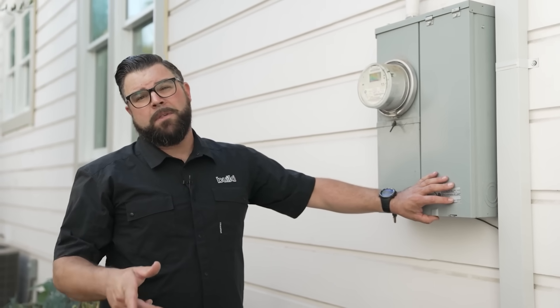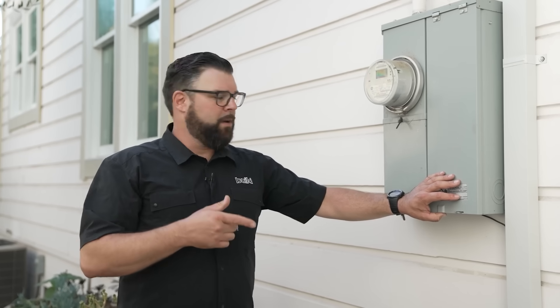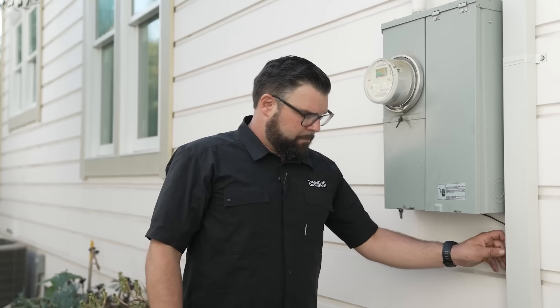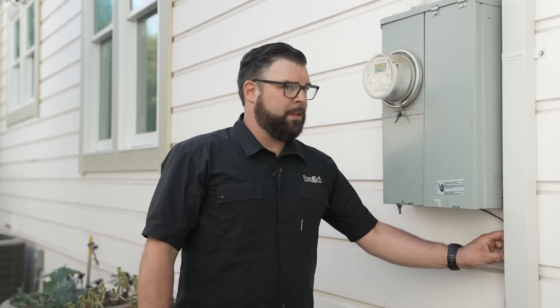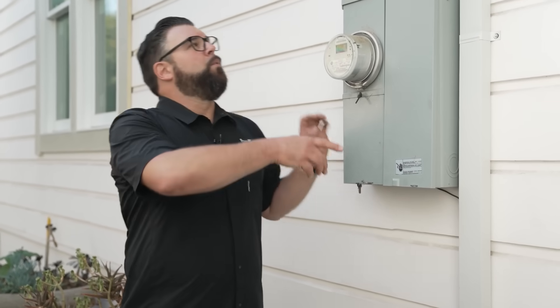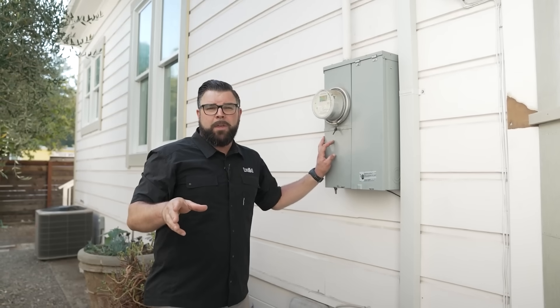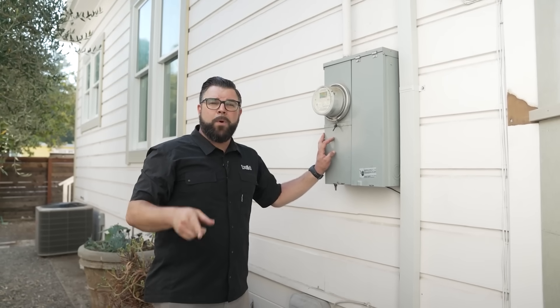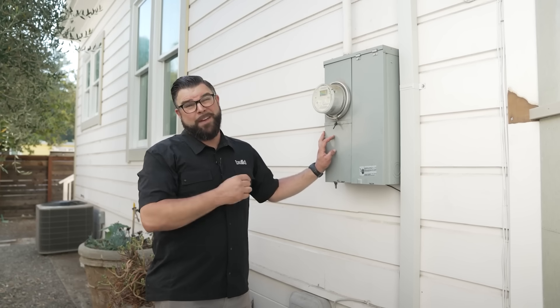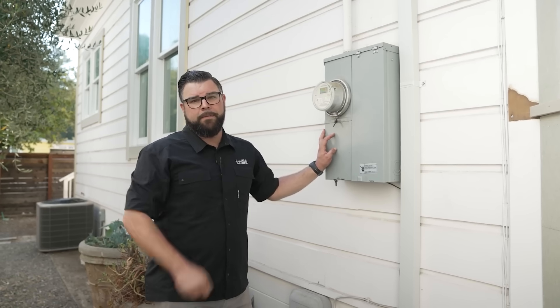100 amps is the weak spot, but 100 amps in a modern grounded service is a crucial one. Inspectors will flag this, but check ground rods — is your system grounded and what does the service drop look like coming into the house? These are all things you can point out early. If it's an older service, it's going to need an upgrade; this is the heart of the electrical system and could be costly. It shouldn't scare you away, but you should be aware of it.